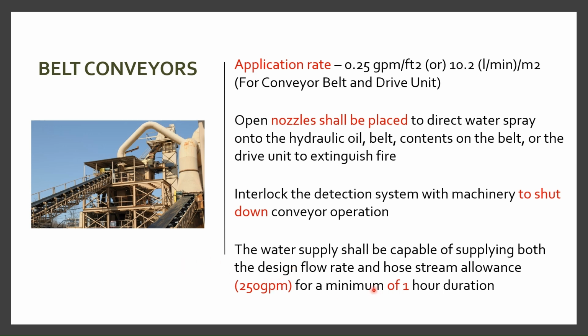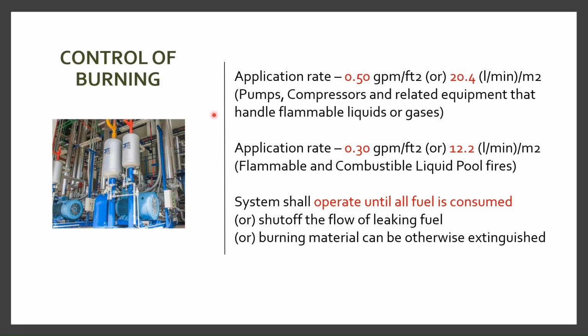And in order to select it, the water tank or the fire pump shall be capable of supplying water for 1 hour duration. Now, control of burning. If you have pumps, compressors and related equipment that handle flammable liquids or gases, we need to consider the design density as 0.50 GPM per square feet. And if you have liquid pool fires, flammable and combustible type, then the application rate will be 0.30 GPM per square feet. The water spray system shall operate until all fuel is consumed, the flow of leaking fuel is shut off, or the burning material can be otherwise extinguished.